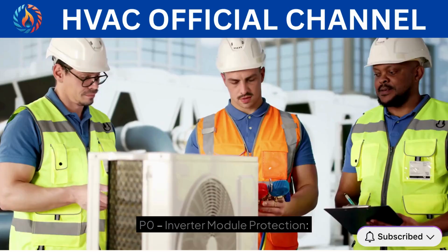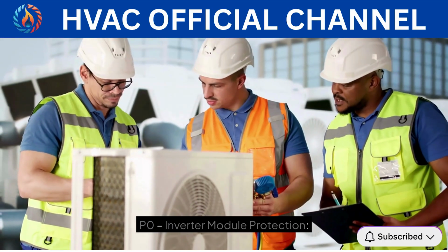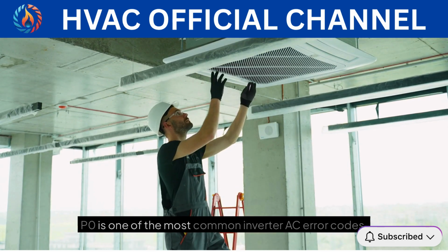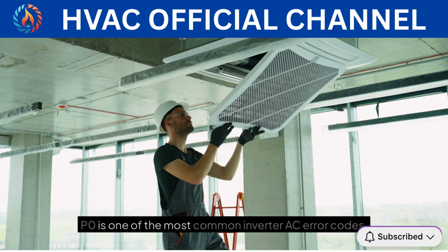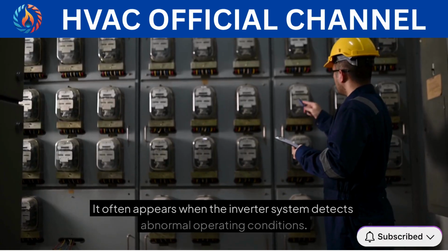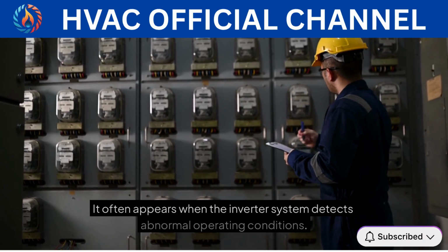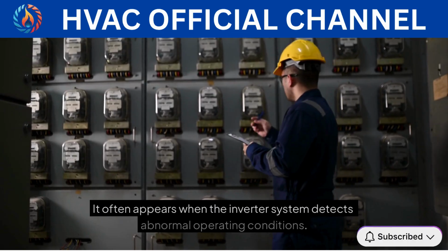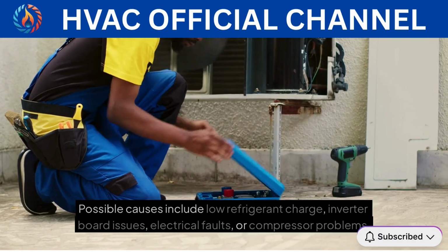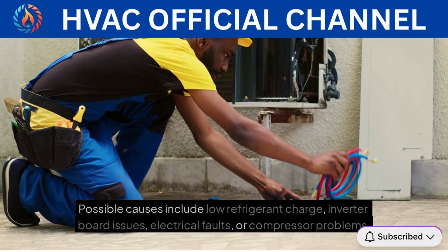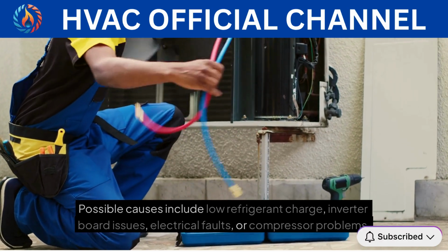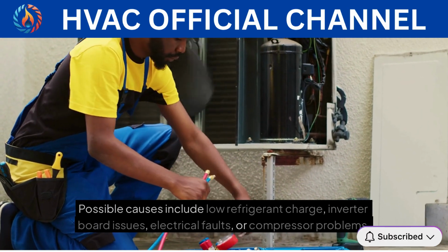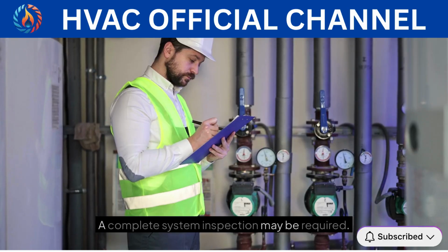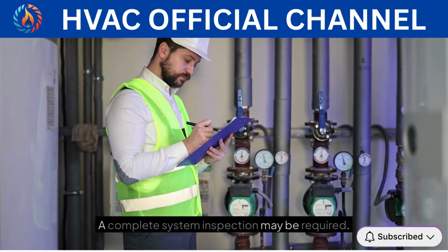Error code 8, P0, inverter module protection. P0 is one of the most common inverter AC error codes. It often appears when the inverter system detects abnormal operating conditions. Possible causes include low refrigerant charge, inverter board issues, electrical faults, or compressor problems. A complete system inspection may be required.